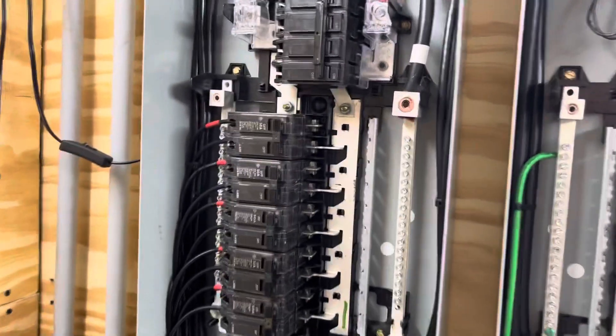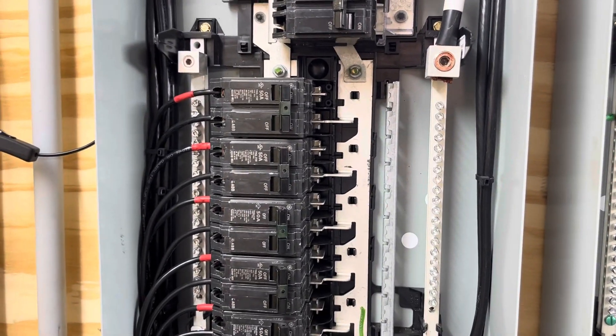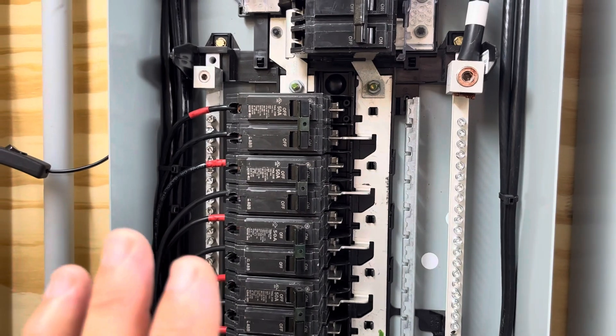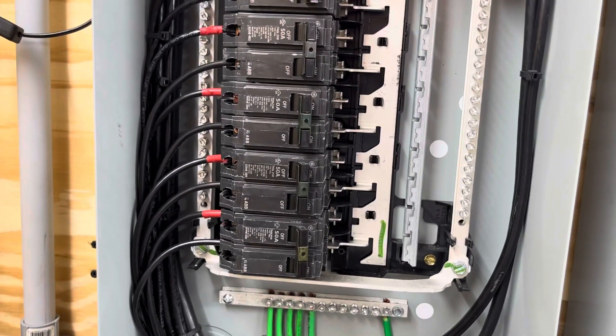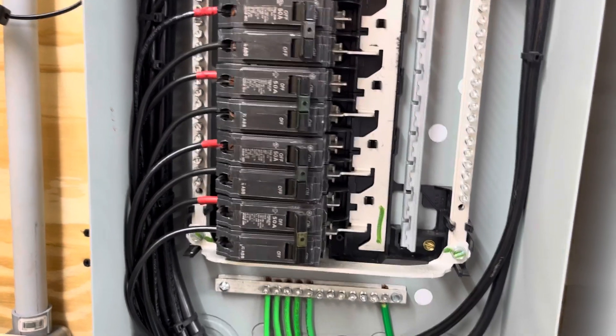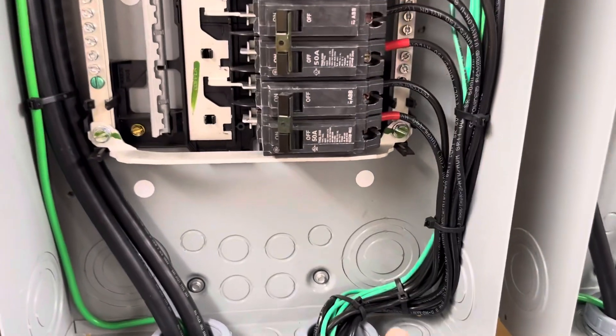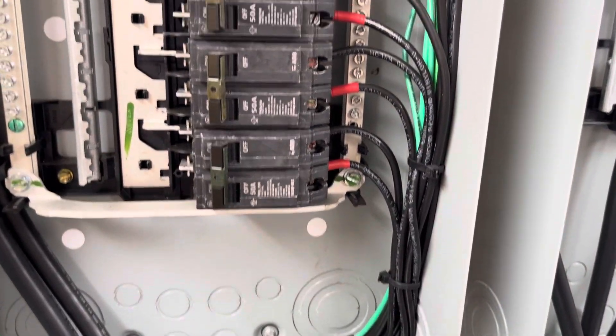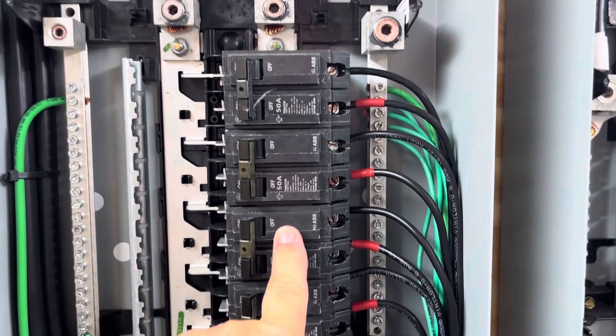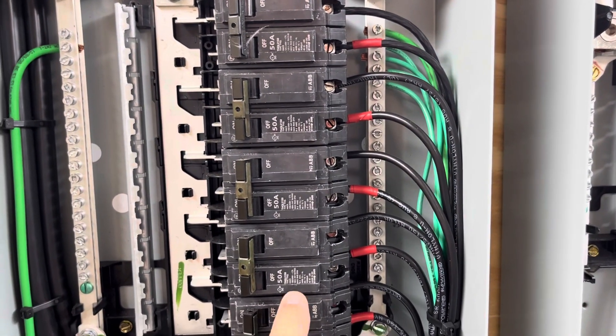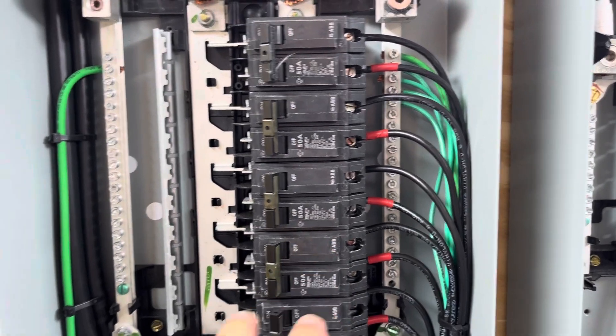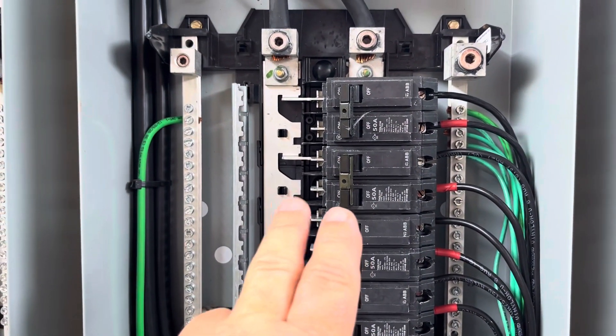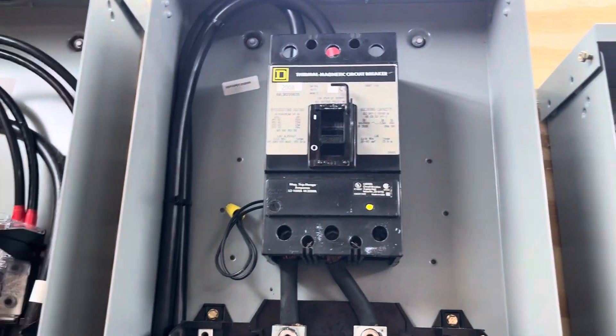So, as you can see, this is my utility input panel, an inverter input panel from the utility. Strictly 240 volts going to the inverter and a ground. Coming from the inverter are these conductors here. Each inverter is fed into the load side of this breaker. It's back-feeding the breaker, energizing the bus, and then it comes out of this breaker here.